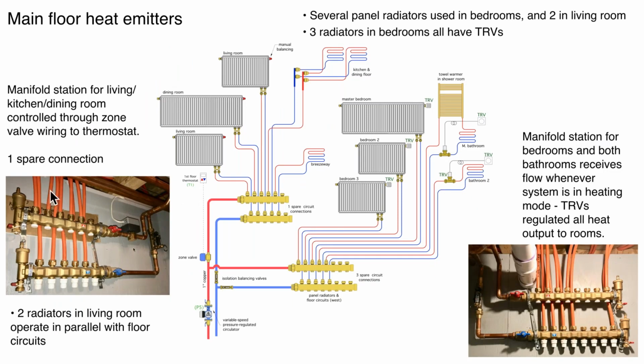Here's the manifold. There's that zone valve; this goes up to this collection of circuits here. There's another manifold that goes up to this collection of heat emitters over here. And you can see we've left some spares. I would suggest to you, leave at least one spare connection on each manifold. That way, if somebody does an addition on the house or they want to put another panel rad somewhere, very easy to tie that tubing right back in. You don't have to do any extensive modification to the system. Just run the tubing through the framing and isolate the manifold temporarily, shut these valves off, and make your connections.